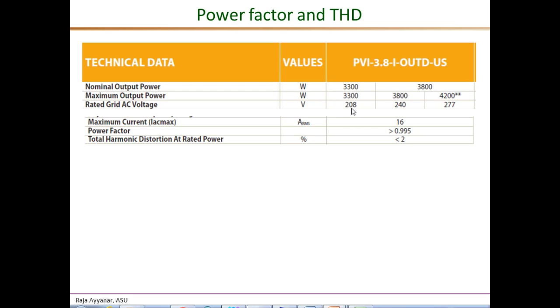The first performance measure we will look at is the power factor of the inverter. Almost all string inverters operate at exactly unity power factor, so as shown here the power factor of this particular product is very close to one. The power injected by the inverters is limited by the current rating, which for this product is 16 amperes. Unity power factor operation ensures that we inject the maximum possible power for a given current rating, and that is the reason why most inverters operate at unity power factor.